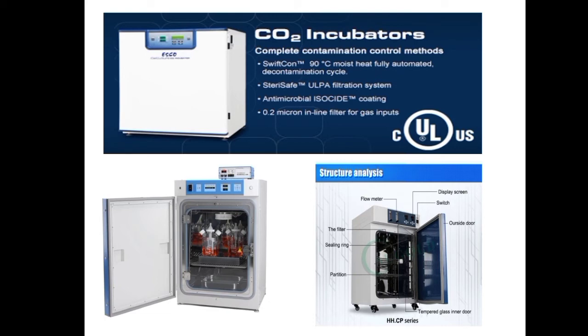If we talk about the structure of the CO2 incubators, it has an interior which is completely sealed off from the environment to ensure the atmosphere inside the unit cannot be affected by external factors.